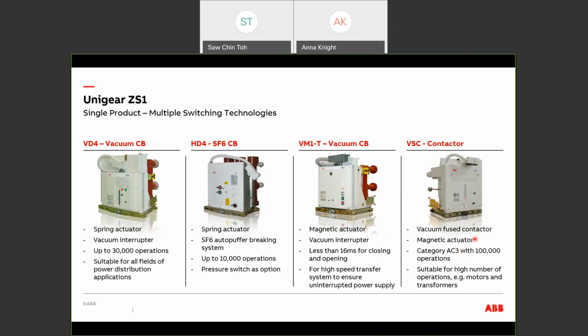For motor applications where frequent switching is required, we have the VSC fuse contactor. This contactor is classified as AC3 with 100,000 operations. The mechanical life for such a contactor is 1 million operations. It is very robust, designed for customers who are planning to switch the motor a few times a day.